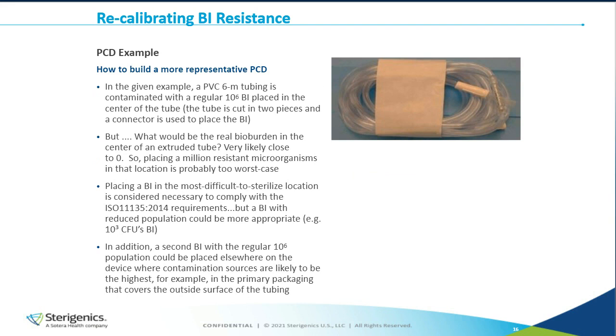Now I'm giving you an example of how we can get away from what has been done before. In my example here, we have a 6-meter PVC tubing that has been used forever as a PCD for a customer, and we place a 10 to the 6 BI in the center. So we cut the tubing in half, we have a connector, we place the BIs, and we have the worst case item covering the most difficult to sterilize location. Fine.